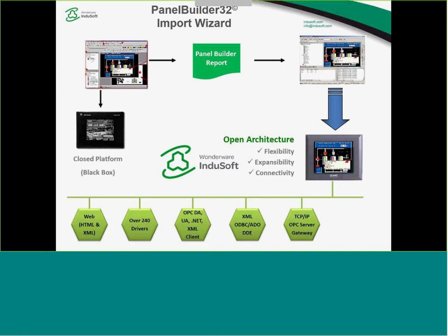So the Panel Builder 32 import wizard allows you to convert applications from the Panel Builder 32 software into an InduSoft Studio application. All the import wizards have 2 main steps. One, you use the old tool to export the project to a set of report files, text files, human-readable files. And step number 2, InduSoft Studio reads the information from those files and creates the screens, tags, animations, alarms, communication interface, creates the application in InduSoft Studio with the same settings from the original one.